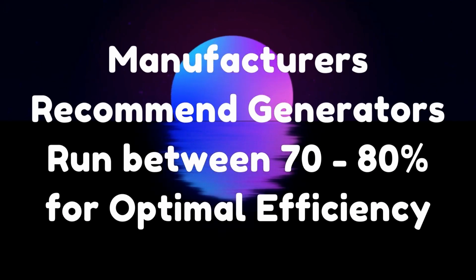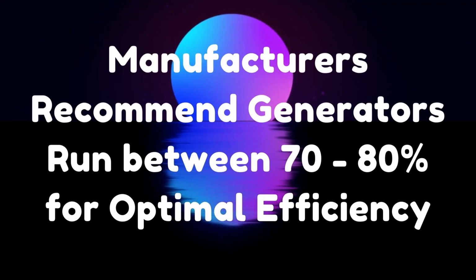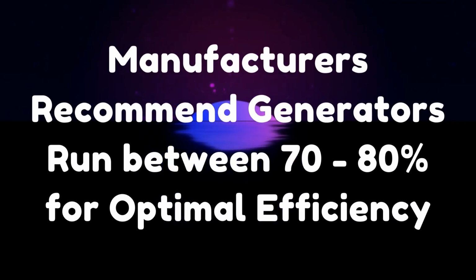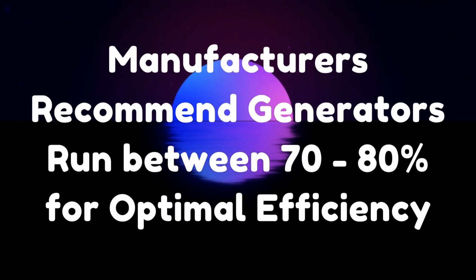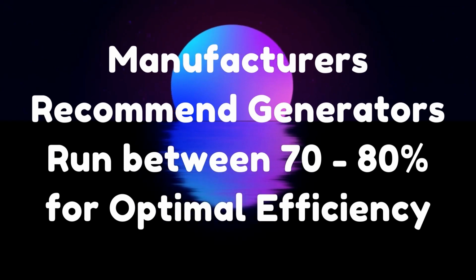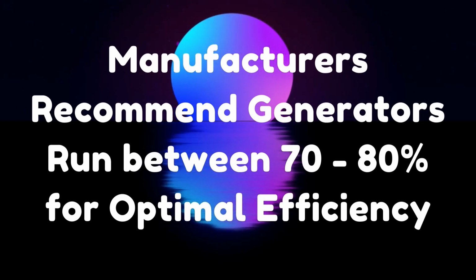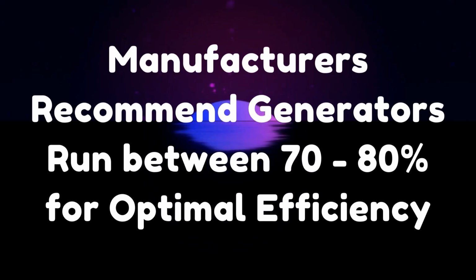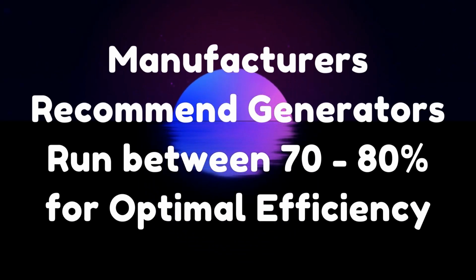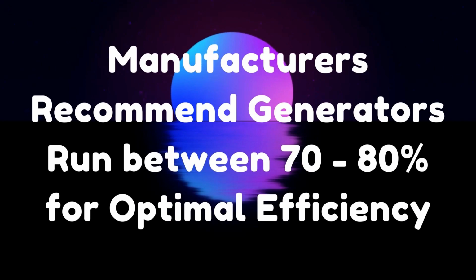Manufacturers generally recommend that a generator should operate between 70 and 80% most of the time. Running within this range ensures optimal efficiency and reduces wear and tear on the generator. It also allows for some flexibility in case of increased demand or additional equipment in the future.